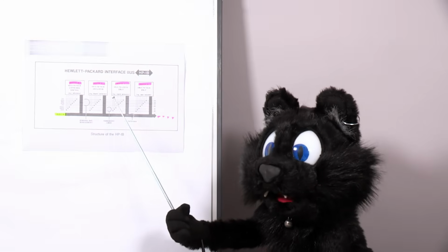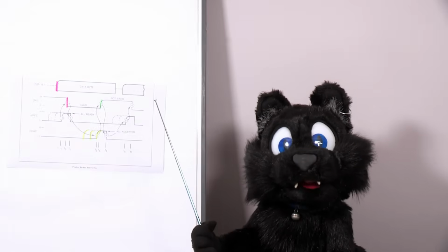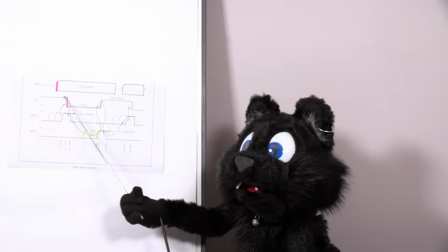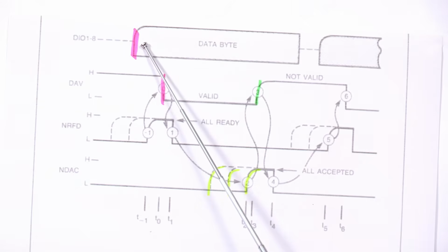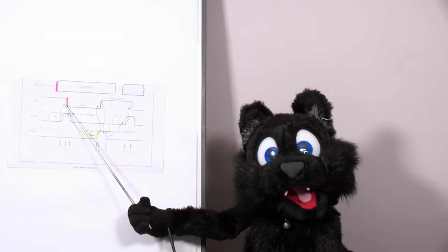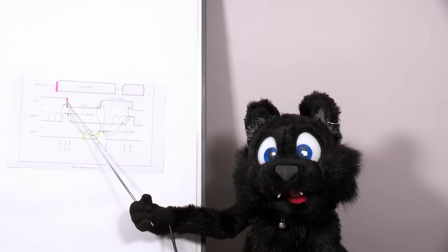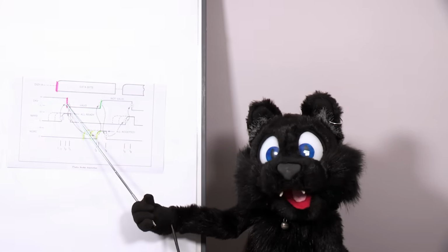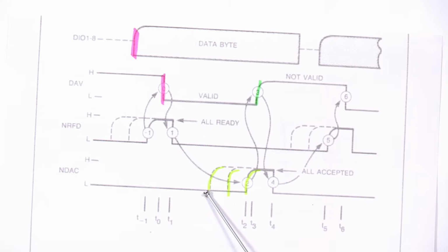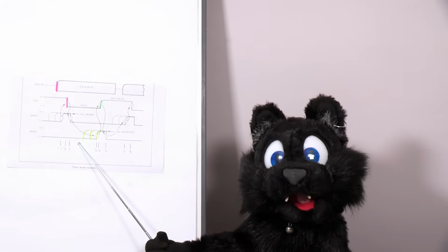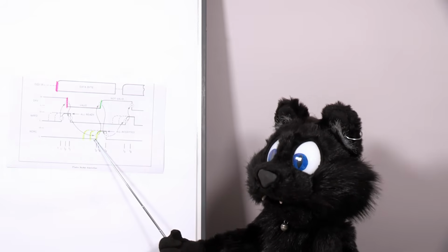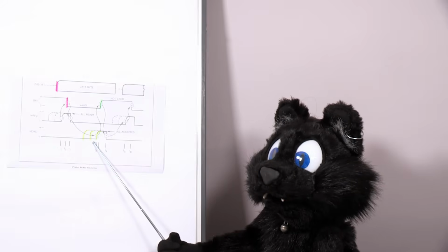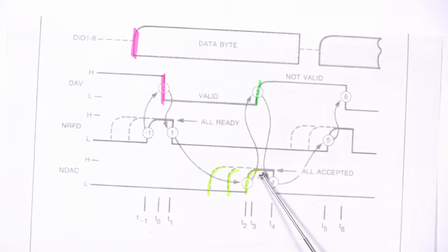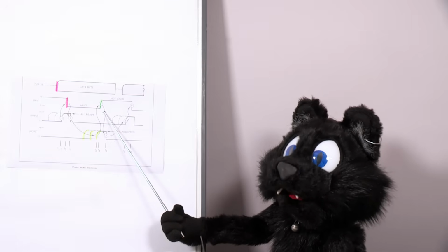All others need to keep them in read access. When the controlling device wants to send a byte to the bus, it first drives the data bits to the desired state and then sets the DAV, data available signal. At this point, every listening device knows that there is data on the bus, and it reads that data into a latch of sorts. Once the listener has the data, it releases the NDAC line. NDAC is not data accepted. It is driven low by all devices that are listening but have not yet read the data bus. When nobody is driving this low anymore, a pull-up resistor will make it go high on the bus, thus telling the controller that every device has successfully read the current byte.